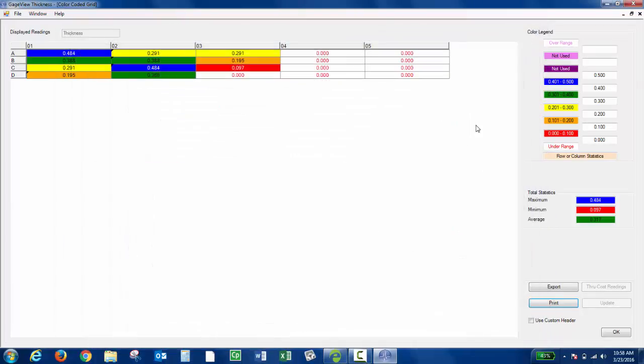If I was doing like a thru-coat or an oxide or a temperature compensation file, the special thickness measurements will be displayed here as well. I'd have the option to choose like alternate reading or thru-coat.